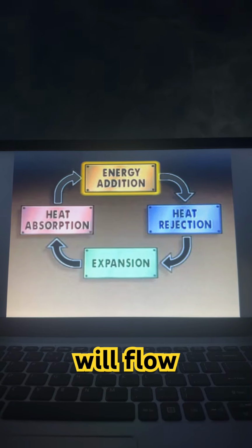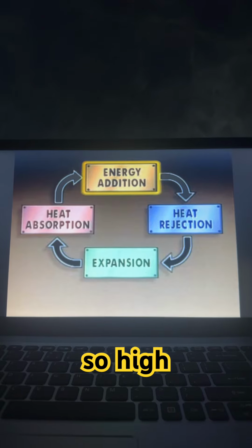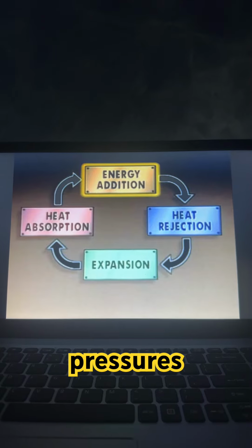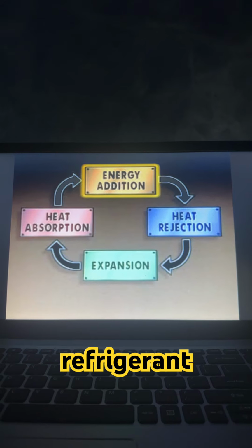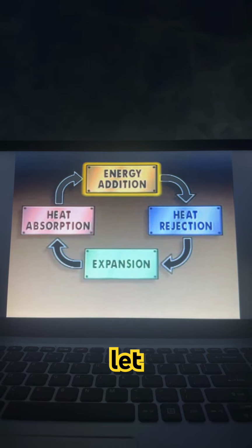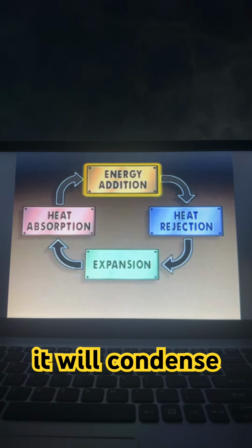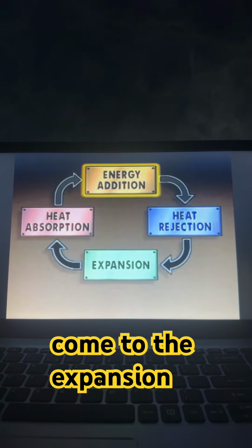So low temperature coolant, like water, will flow through here. The high temperature, high pressure gas, the vapor from the refrigerant, rejects its heat and changes phase. It gives up the latent heat of condensation, then it condenses and becomes liquid. After becoming liquid, it comes to the expansion.